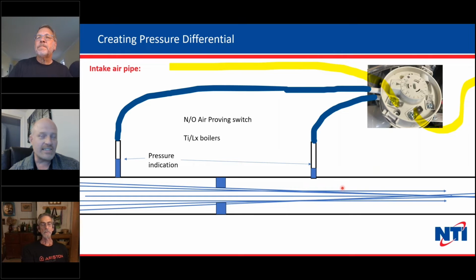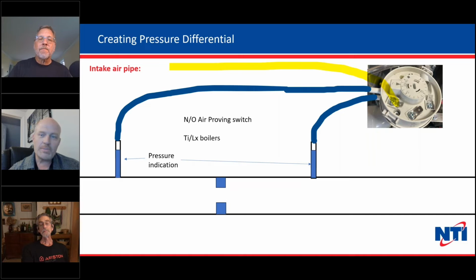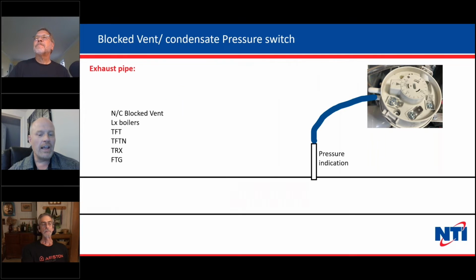And we can then set the switch to a reading. So the old TI switches were always set at 2/10 of an inch water column or 0.2 inches water column. And when everything was working right, that meant you had enough air moving in order to create the correct pressure difference to run the burner safely. So when the air stops, the pressure drops or increases to a normal reading because when you're not sucking on the pipe, of course, the pressure is going to go back up again. And that means we have no airflow.